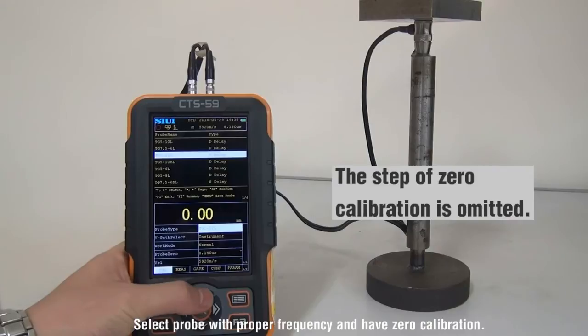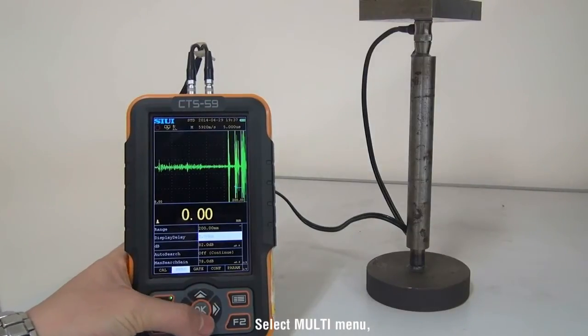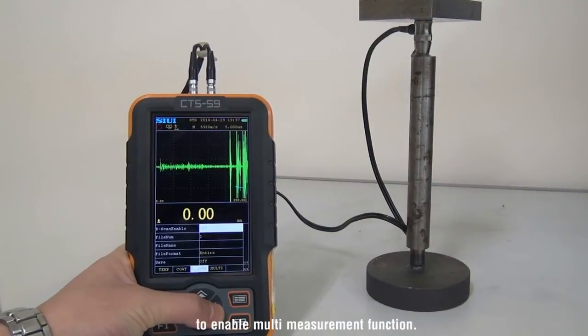Select probe with proper frequency and have zero calibration. Select Multi-Menu, adjust Multi-Measurement Enable to On to enable Multi-Measurement function.